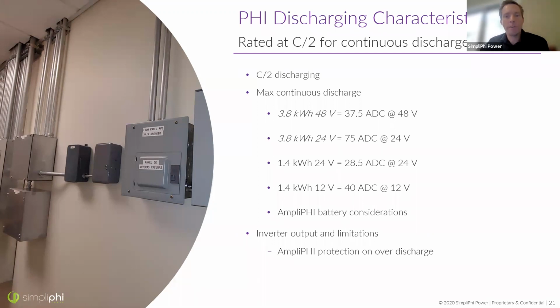Our smaller battery, of course, has a smaller discharge rate. The current ratings given to you there are 28.5 amps for the 24 volt and 40 amps for the 12 volt. Notice that when you halve the voltage on the Phi battery and go to the 24 volt battery, you get twice the current. Same amount of power output on both. Power is current times voltage, so both are capable of 1.9 continuous kilowatts of output.